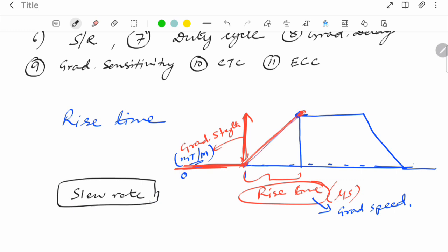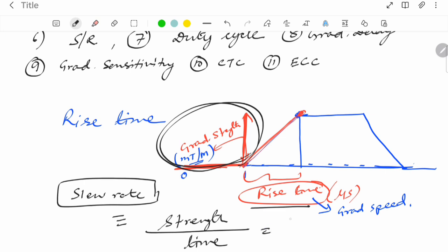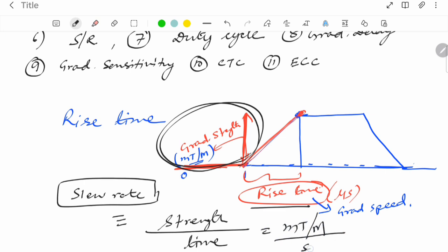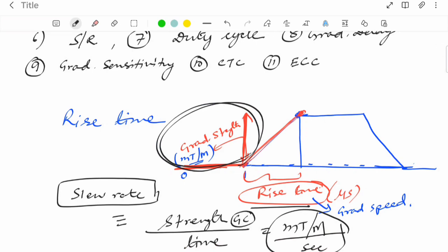The commonly used term is slew rate. Slew rate is the strength of the gradient over time — gradient strength divided by rise time — measured in milli-tesla per meter per second. So slew rate is the strength of the gradient over time.